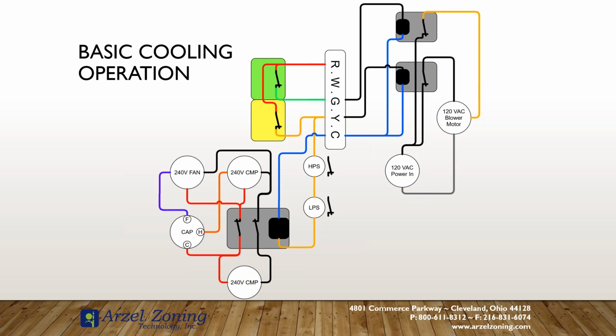So that basic cooling operation, our G call comes in, and that starts our blower. Our Y call comes in, and that starts our blower on high speed. Now that Y call then goes to the outdoor unit. If it's a really basic outdoor unit, it may or may not have high pressure and low pressure switches. This is a call I get often enough, and it's going to start up here pretty soon because spring is here. People are starting their preventative maintenance checks for cooling, but they'll be at the RSL panel and they'll say that it looks like it's calling, but my outdoor unit's not working.